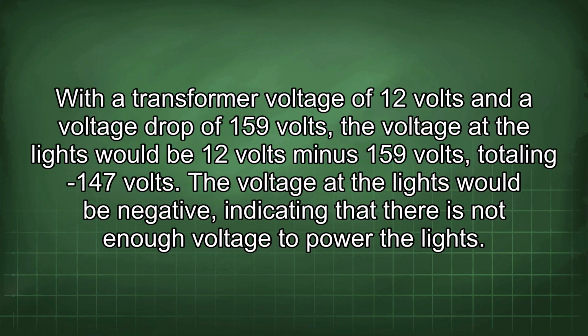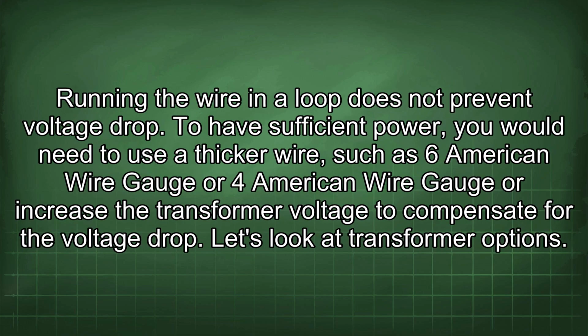With a transformer voltage of 12 volts and a voltage drop of 159 volts, the voltage at the lights would be 12 volts minus 159 volts, totaling minus 147 volts. The voltage at the lights would be negative, indicating that there is not enough voltage to power the lights. Running the wire in a loop does not prevent voltage drop. To have sufficient power, you would need to use a thicker wire, such as 6 American wire gauge or 4 American wire gauge, or increase the transformer voltage to compensate for the voltage drop.